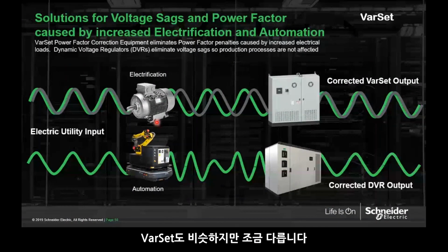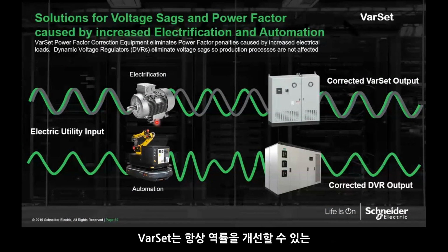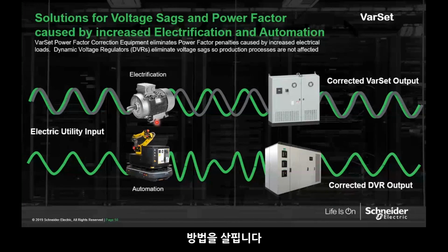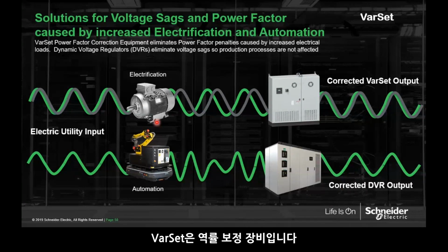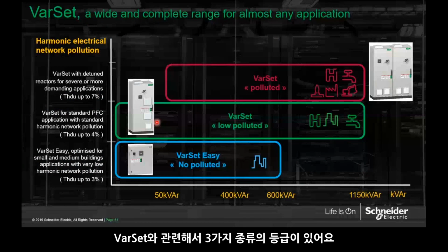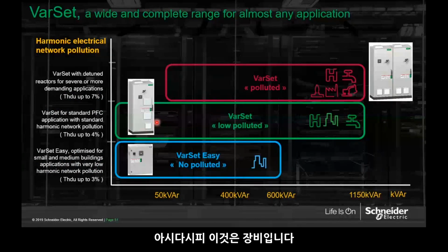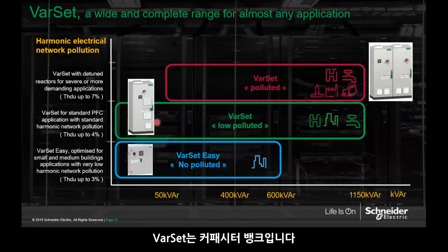Then the same thing for VARSET. VARSET is a bit different. VARSET is always looking more at how we can improve the power factor. Power factor is mainly for the VARSET. It's power factor correction equipment. In terms of VARSET, we have three different ratings. As you know, this is an equipment, not a component. It's not a capacitor. It's a capacitor bank, and it's a type tested capacitor bank.